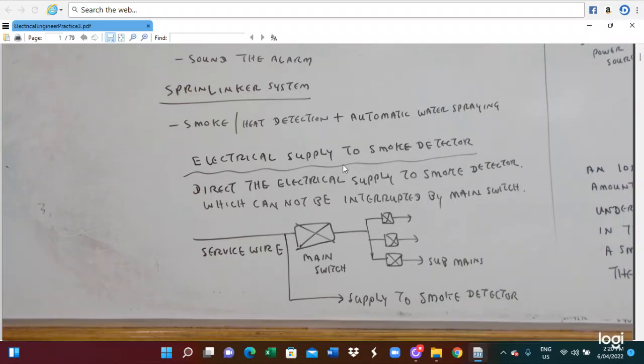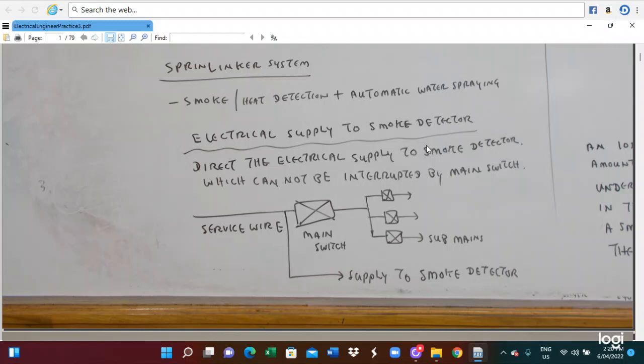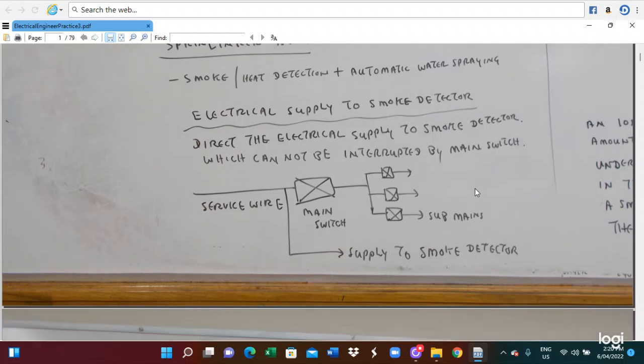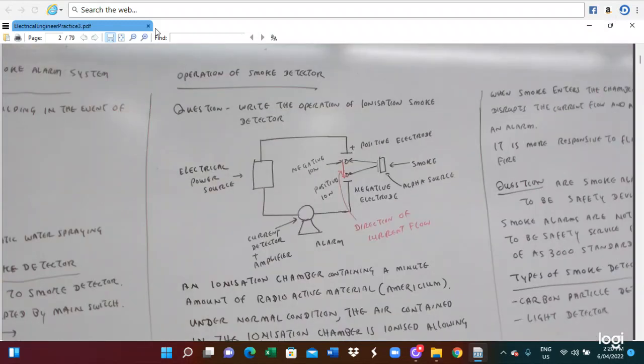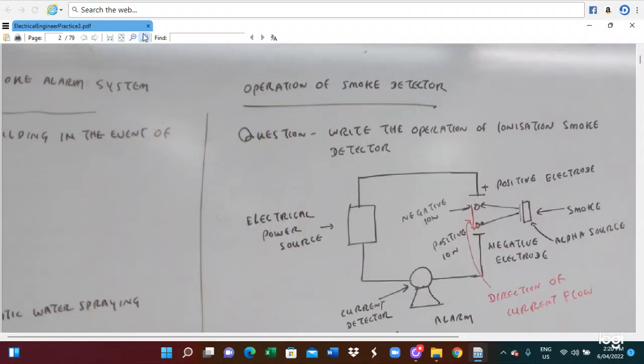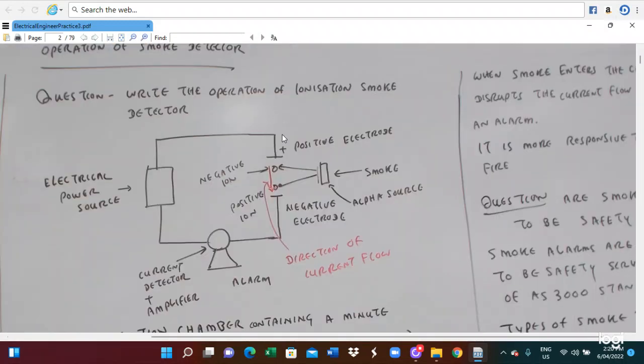The electricity supply to the smoke detector system cannot be interrupted by the main switch. This is the sub main, this is the main switch, this is the sub main, but here it is directly connected to the smoke detector system. This is just the operation of the smoke detector system.